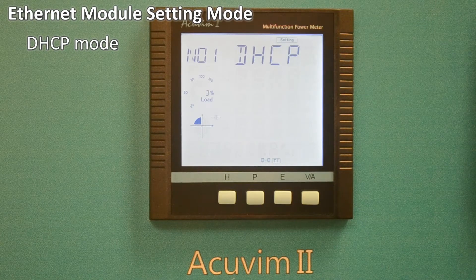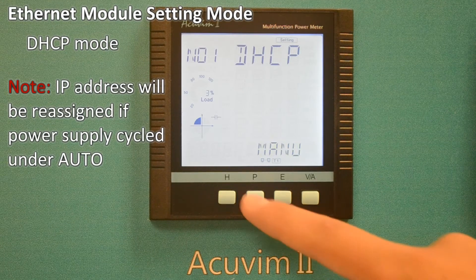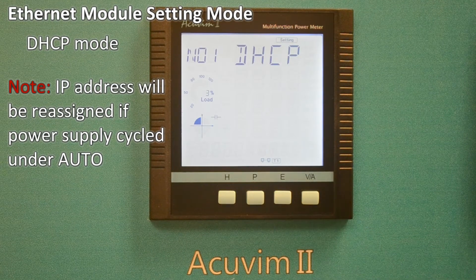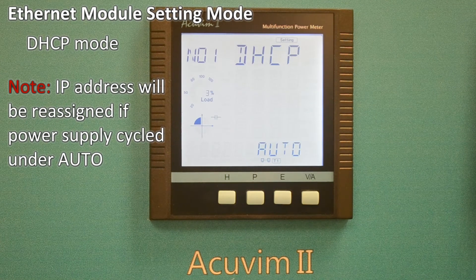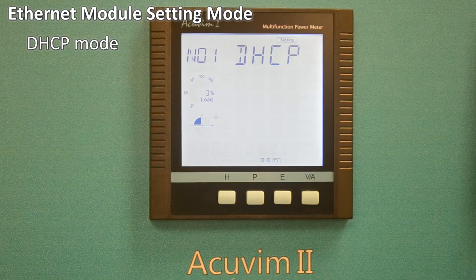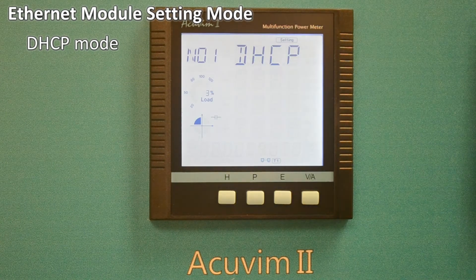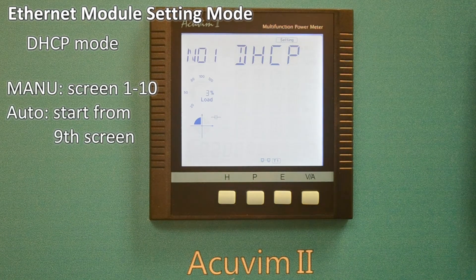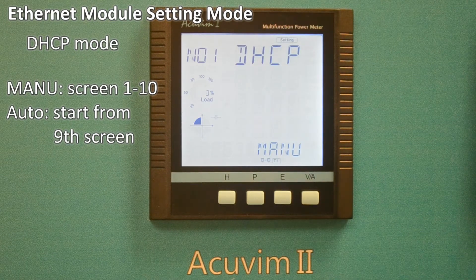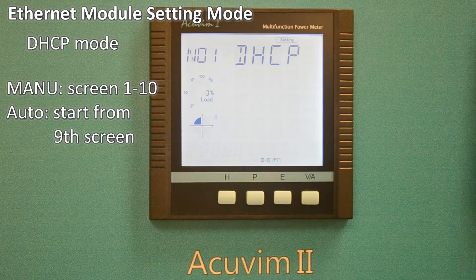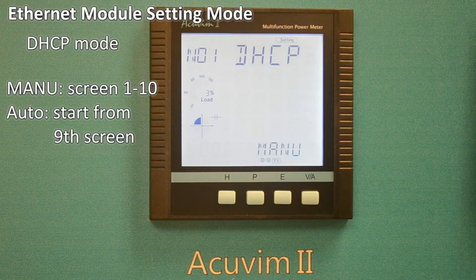Please note: under Auto setting, the IP address on every meter will be reassigned if the power supply is cycled. We will now demonstrate the steps for Manual settings from the 1st to the 10th screen. If you select Auto settings, please skip ahead and start from the 9th screen.